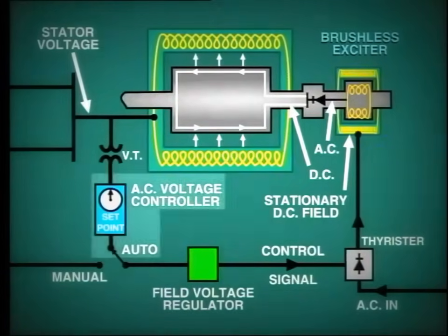When in auto, the field voltage regulator receives its command signal from the AC voltage controller, which in turn monitors the output voltage of the generator. The operator can adjust the AC set point as required. When starting up the unit, the field voltage regulator may be set to manual and in this case, the operator will control the regulator directly.